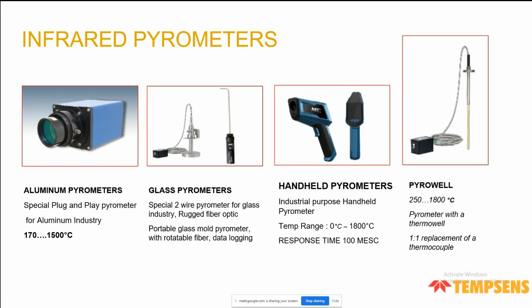People are worried about buying a Pt-Rh/Pt thermocouple, so this is a solution. We have put a pyrometer on top of a standard ceramic thermowell. The pyrometer is at the end, with the electronics giving a 4-20 milliampere output, and also, if you want a 1:1 replacement, it can give you an R-type, S-type or B-type equivalent millivolt output, so you don't have to change your cable. We call this a pyrowell, and we've applied for a patent for this product. You can replace a thermocouple with it, and today it might even be cheaper than a platinum thermocouple.